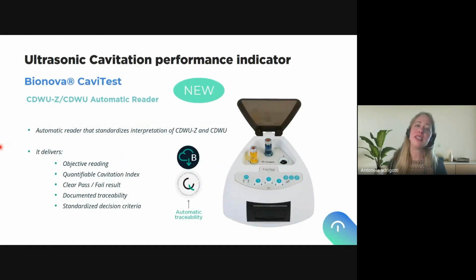So what is our solution? And this is a new product, Bionova CaviTest, which is in the end an automatic reader of the cavitation indicators. Okay, so this automatic reader standardizes the interpretation of both these indicators, delivering objective reading, quantifiable cavitation index, clear pass-fail results, documented traceability, and standardized decision criteria. As you can see on the screen, it has 3 positions. This is an automatic readout. There is no incubation. You just place the indicator in one position, press the corresponding button of that position, and automatically the auto reader will give you a result.